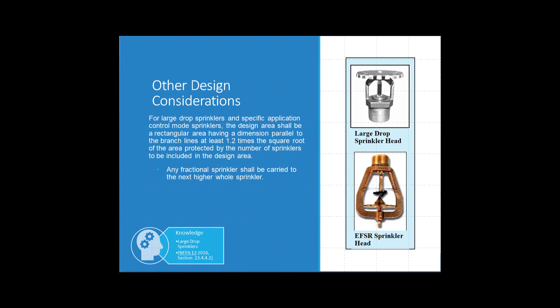For specific application control mode sprinklers, the design area shall be a rectangular area having a dimension parallel to the branch lines at least 1.2 times the square root of the area protected by the number of sprinklers to be included in the design area. Any fractional sprinklers shall be carried to the next whole sprinkler.